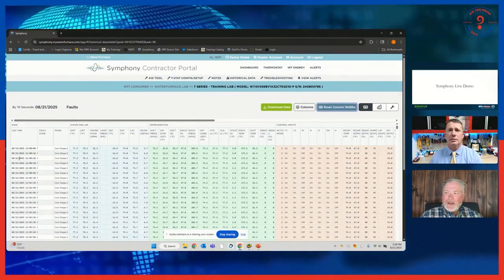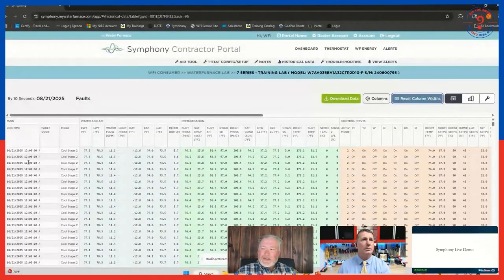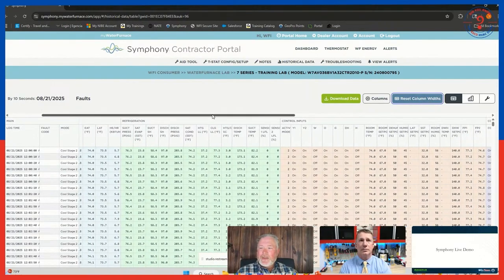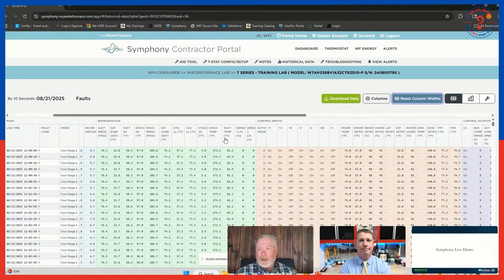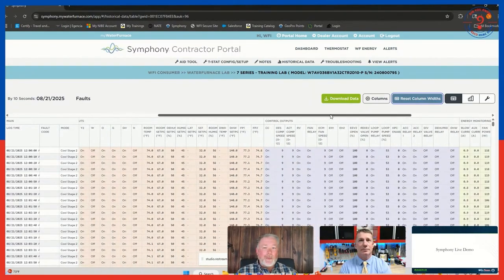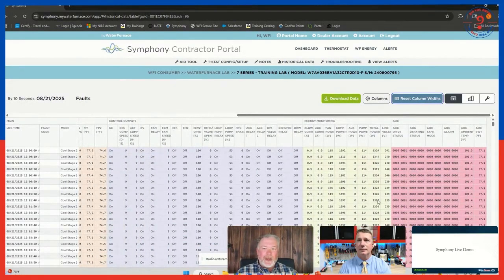I was playing around with it earlier. So on the left-hand side, again, I know this is really tiny letters and it's really hard to see, but the left-hand side is the date and the time. What you can't see here really is that it's taking measurements every 10 seconds. I think there are 97 different points that it's taking every 10 seconds, 24/7, 365 on this unit. So I've got my water and air analysis in the blue. There's all of my refrigeration parameters in the green. There's my control inputs, my control outputs, my energy monitoring, so I can read all of my amps and watts through there. And the right-hand side is drive details.